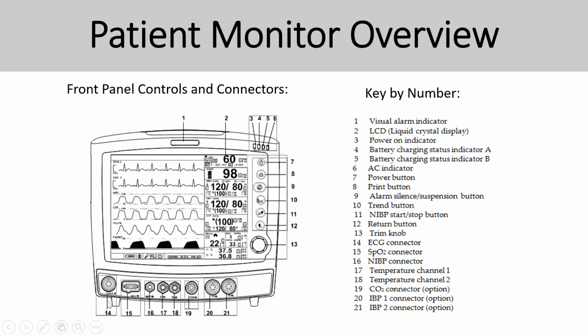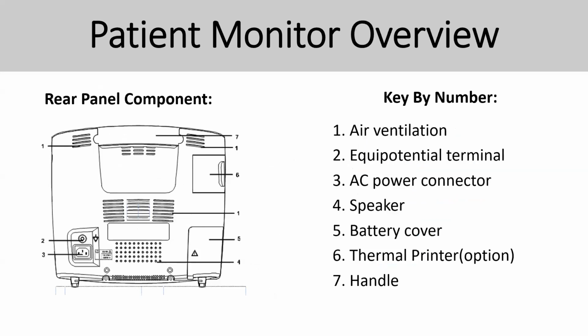At the back view of the patient monitor, you're going to see the rear view of it. You're going to see air ventilation and the equipotential terminal. Depends if the equipment is class 1, you're going to see the equipotential terminal. If class 2, they don't have any particular terminal. So to determine class 1 or class 2 equipment for electrical safety, please look for the symbol of the particular logos for class 1 and class 2 at the rear view of the patient monitor.